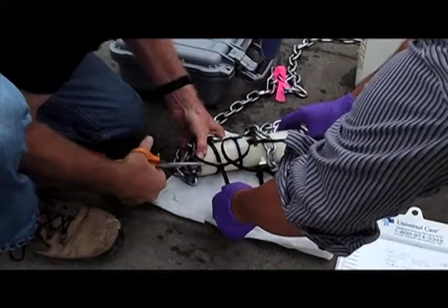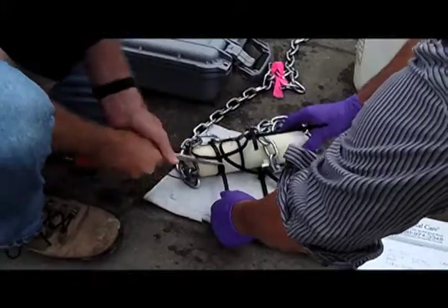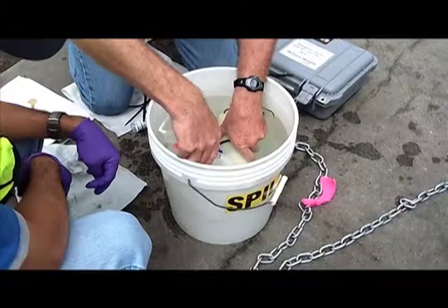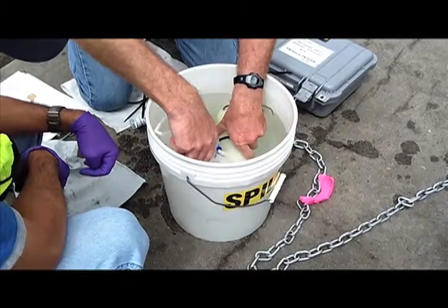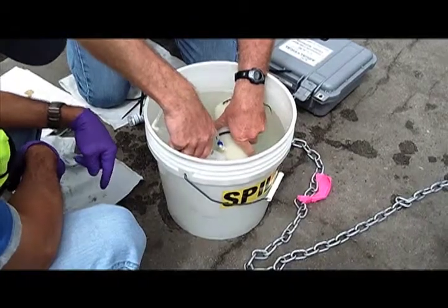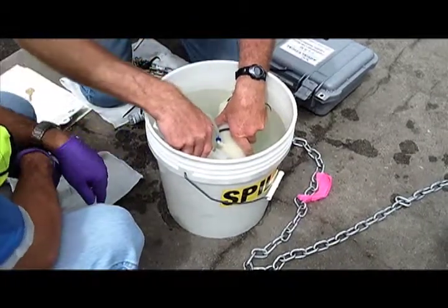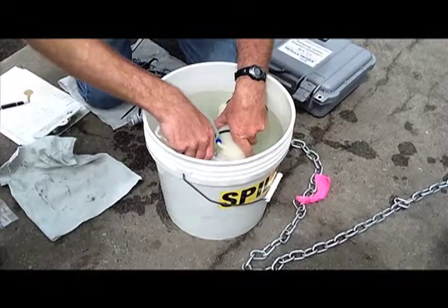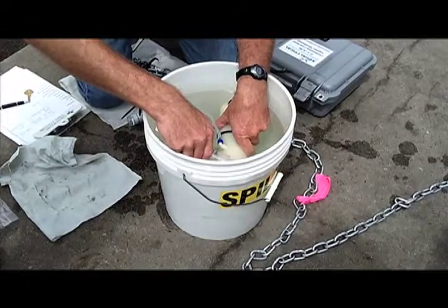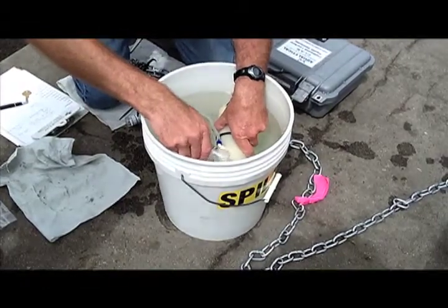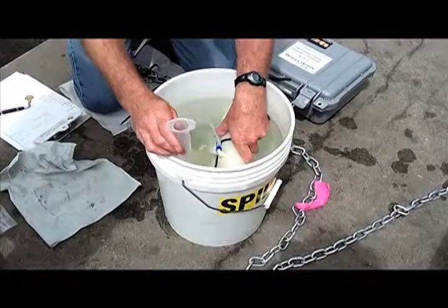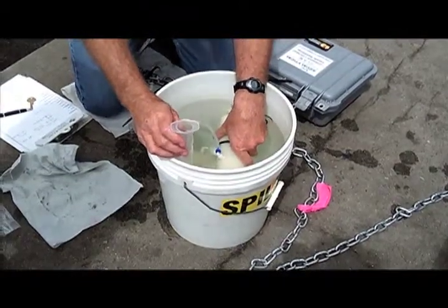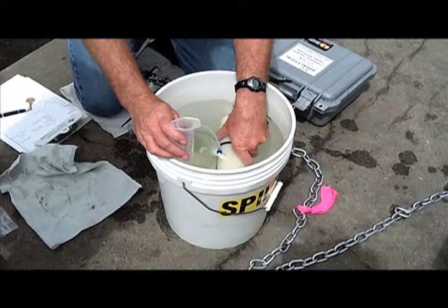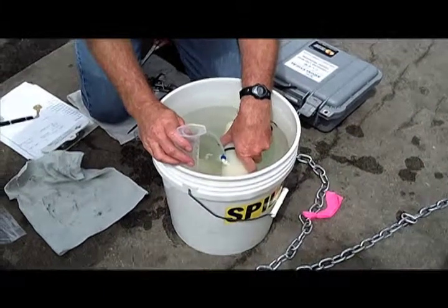Once the tie wraps are cut and the lock is removed, the clamps are placed back in the bucket, and once again care is taken to make sure the air is out of the system before final calibration. It is common for each calibration to get a little bigger flow rate than the last when all of the air is not yet out of the system. That is why we recommend at least 3 calibrations, with the last 2 being identical.